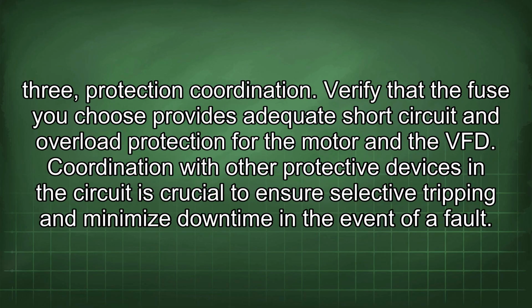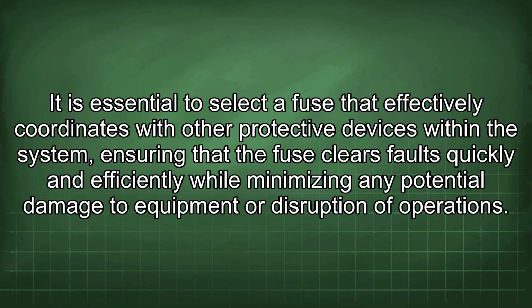3. Protection coordination. Verify that the fuse you choose provides adequate short circuit and overload protection for the motor and the VFD. Coordination with other protective devices in the circuit is crucial to ensure selective tripping and minimize downtime in the event of a fault. It is essential to select a fuse that effectively coordinates with other protective devices within the system, ensuring that the fuse clears faults quickly and efficiently while minimizing any potential damage to equipment or disruption of operations.